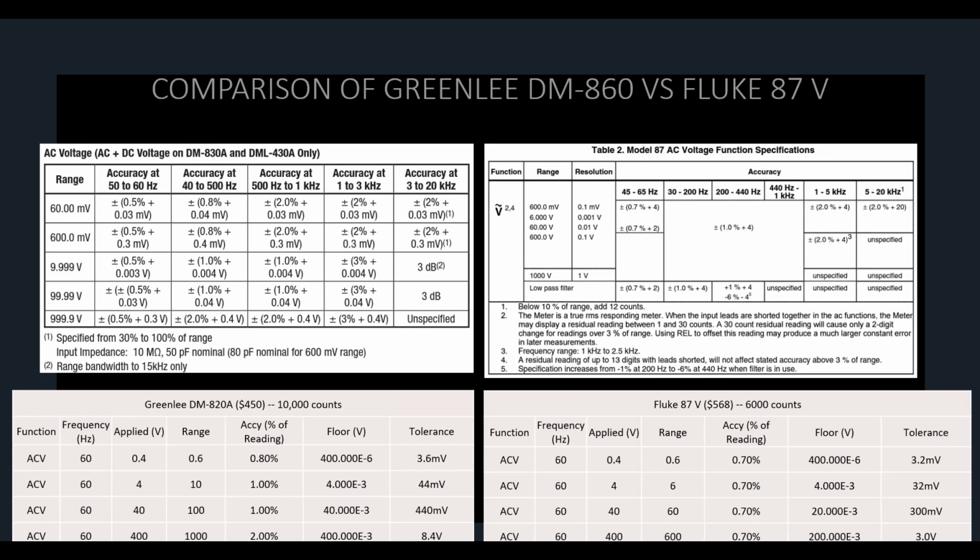So you got different price points for different things and how you can get to what you're looking for. So again, this is where talking to your calibration laboratory before you purchase something can be very helpful, because most of your cal labs, they'll talk to you about, hey, if you're trying to measure 5 microamps, maybe this isn't the meter for you. You should probably be looking at something else, because this is something that we found is that people call us up saying, hey, you calibrated my device, it's not working. Well, what are you using it for? You're using the wrong device. So talk to us.